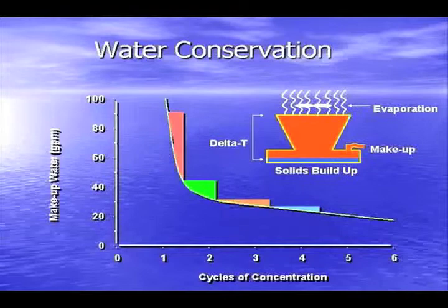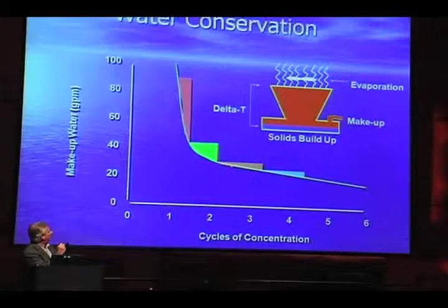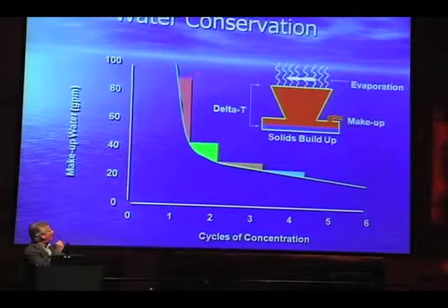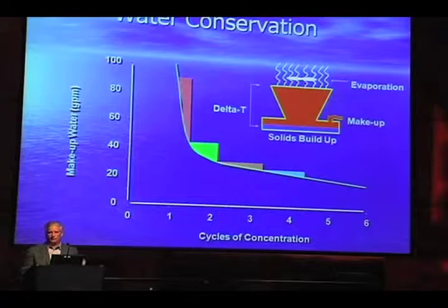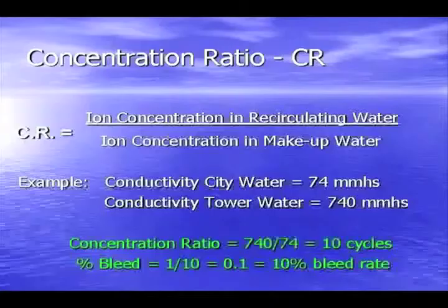Think about water in, water out — that's probably the worst case. If you go to two cycles, you drop almost 50% in water usage. From there, going to three cycles drops a fairly good incremental amount, and then four, five, six, seven, eight, nine cycles continue reducing usage. There is a diminishing return — you can see the graph coming down, and eventually it goes way out. It'll never reach zero discharge. The incremental savings at higher cycles isn't as great, but still worth capturing. If you're running low, the savings are very drastic.